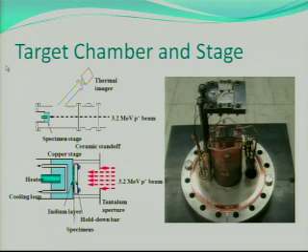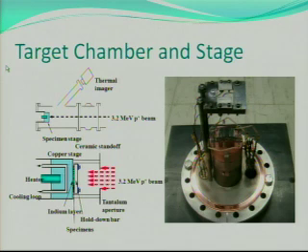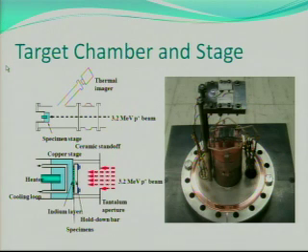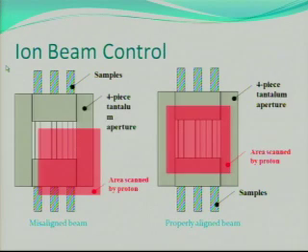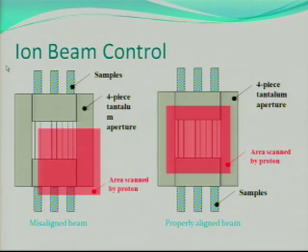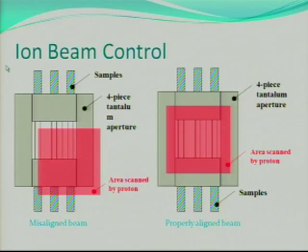The last part is the target chamber. We put the sample on the stage, and above the stage we have four apertures. Only part of the ion beam can go through the aperture and then strike on the sample. Why do we need the aperture? Because we want to align the beam line. The four apertures are electrically isolated, so when the four apertures have the same current, the sample behind the apertures will have the same dose rate.